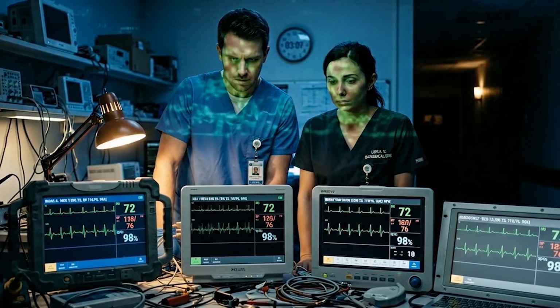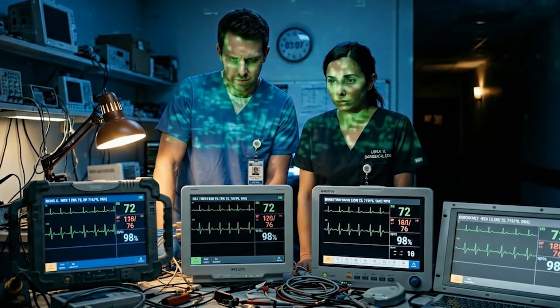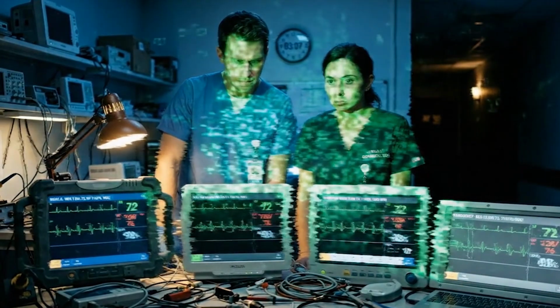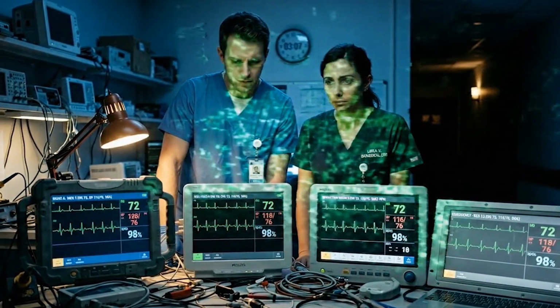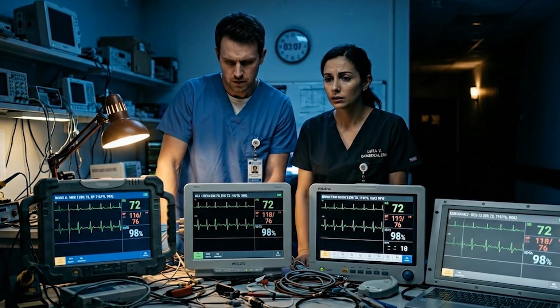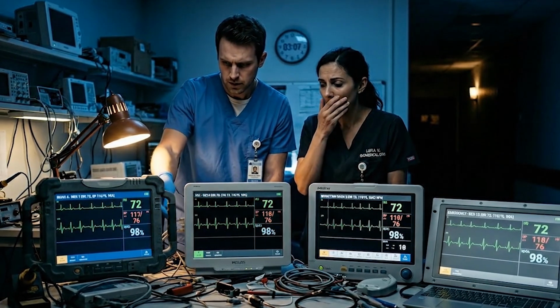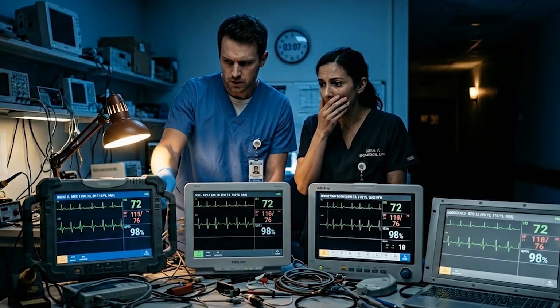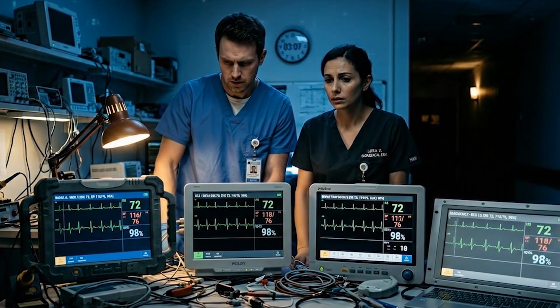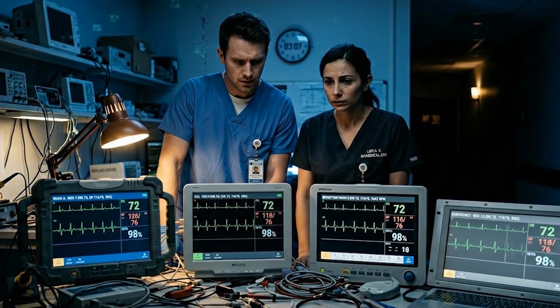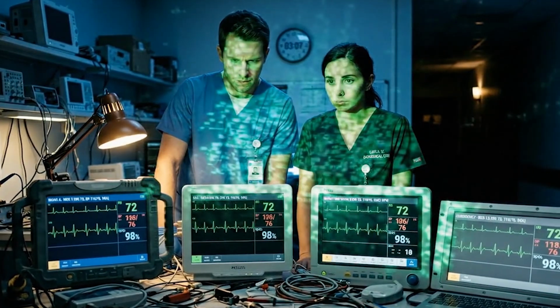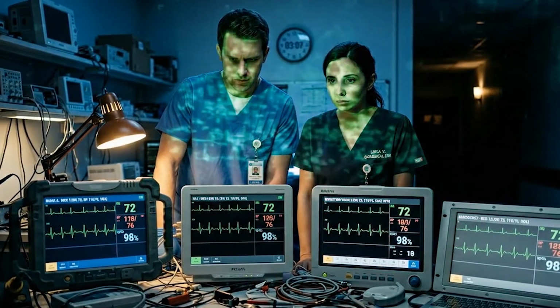A Philips ECG waveform and a GE ECG waveform and a Draeger ECG waveform, even if recording the same patient simultaneously, will look slightly different because the software processes the signal differently. These were identical, not similar. Identical, as if all 3 monitors were displaying the same rendered output from the same source. And that source was not the hardware or the software or the network, but something else.